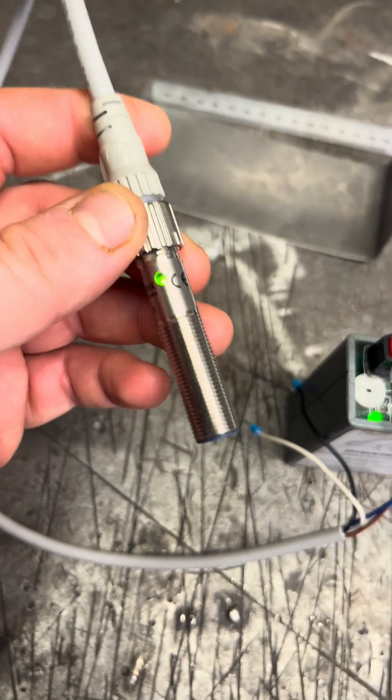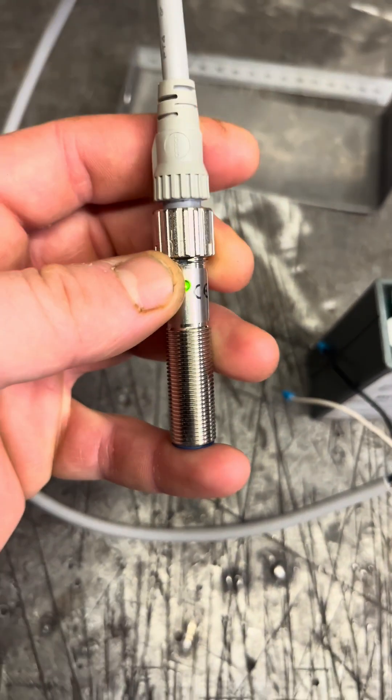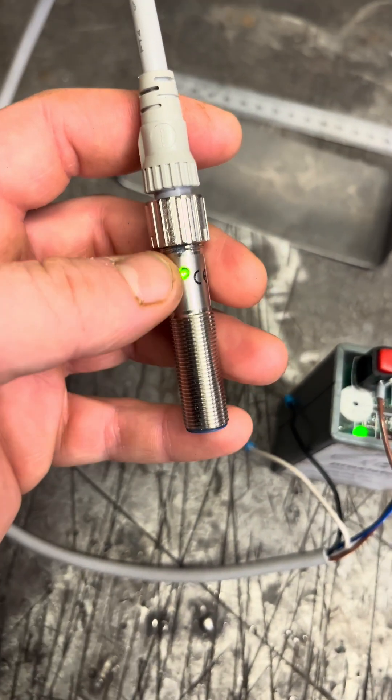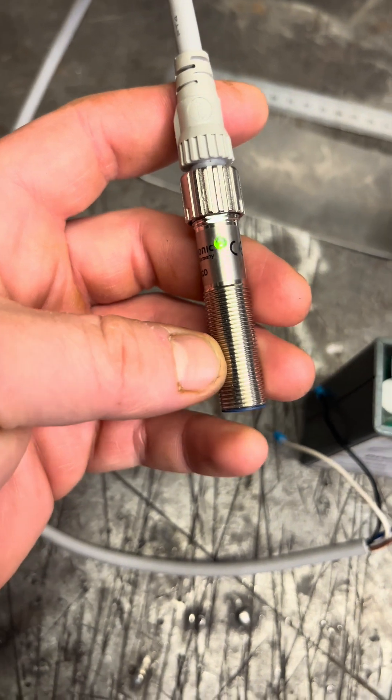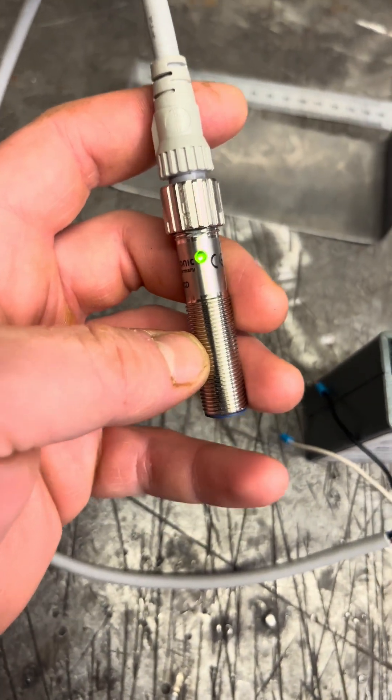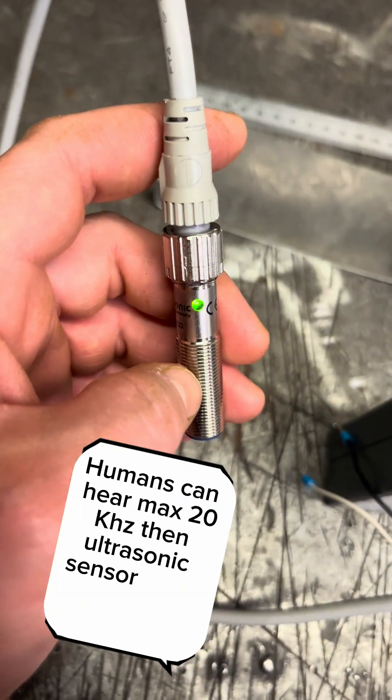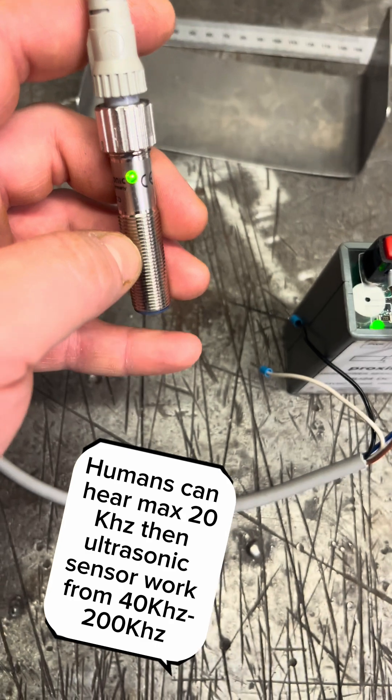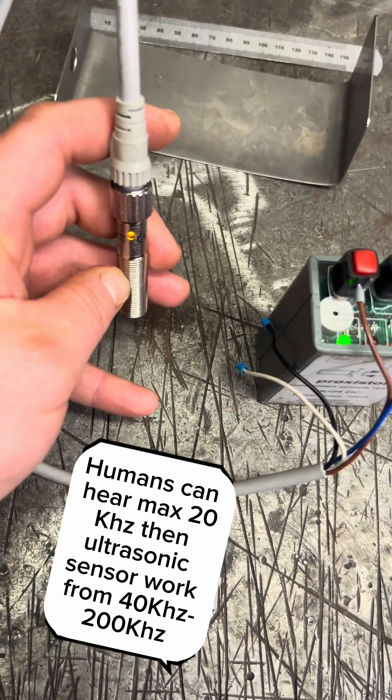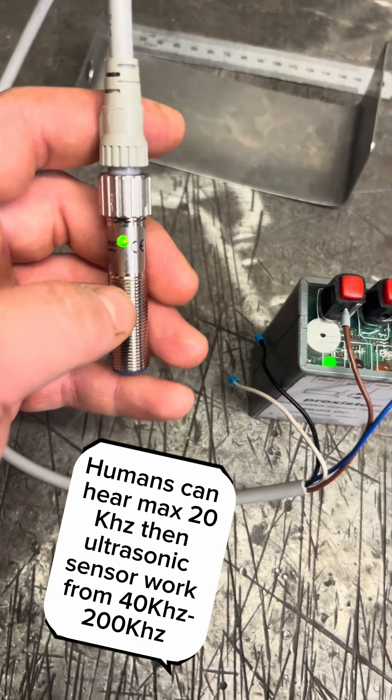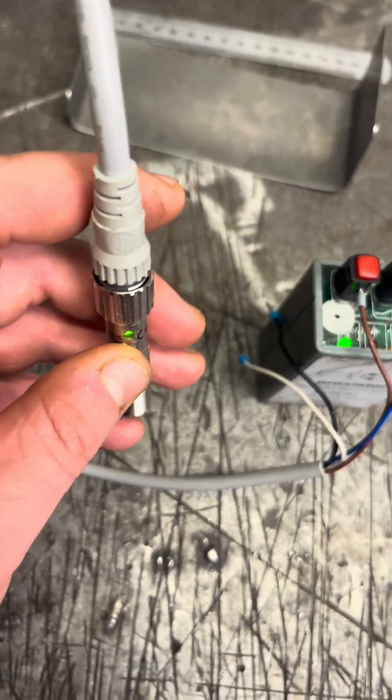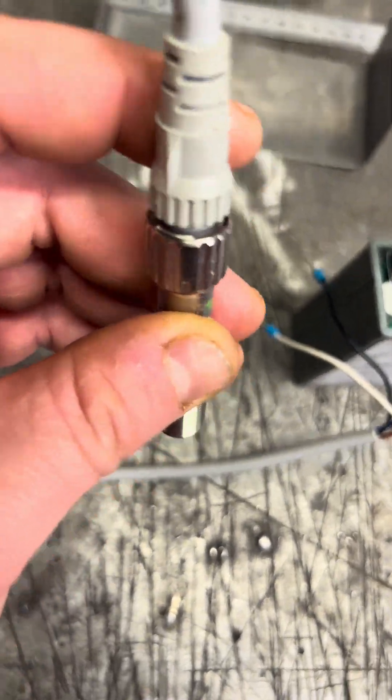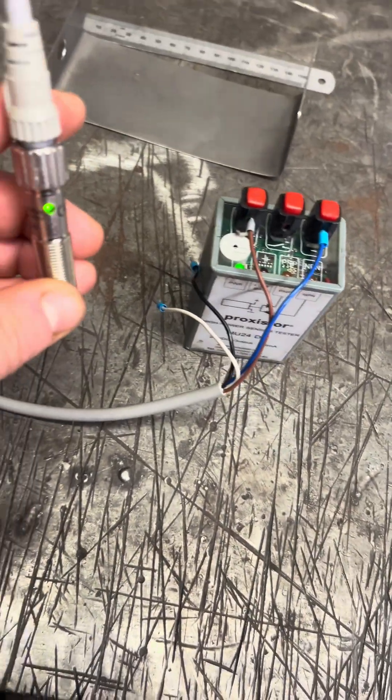So how ultrasonic sensor works is we've got an electronic signal being sent down to a piezo transducer, and that is converting it into a sound wave. And what that's doing is that's being sent out, bounced back, and then that's being timed. That's called timing of flight. And then that's done around about five times every second.